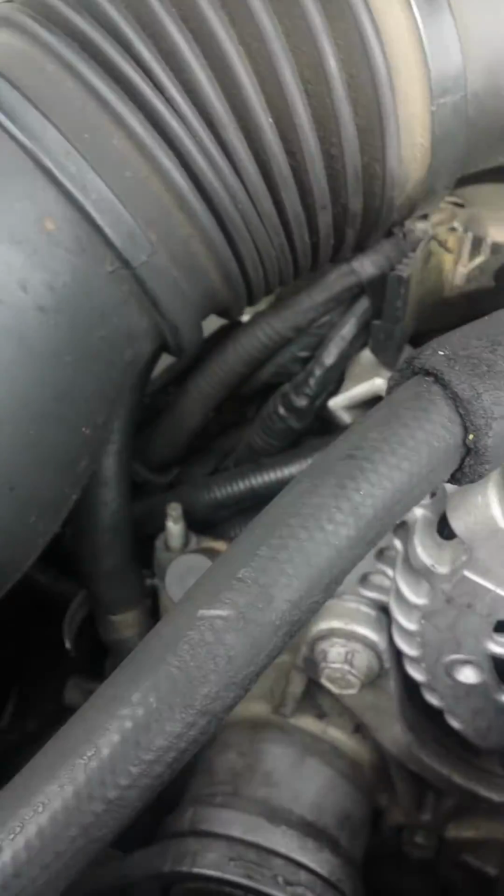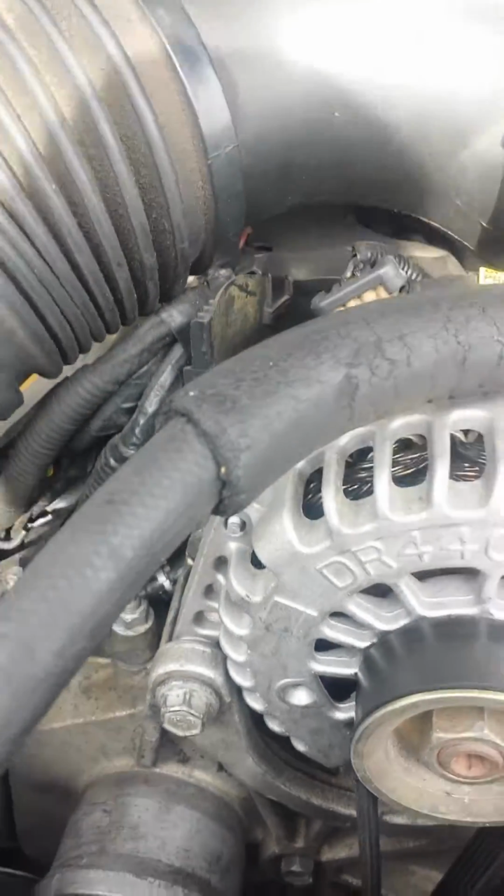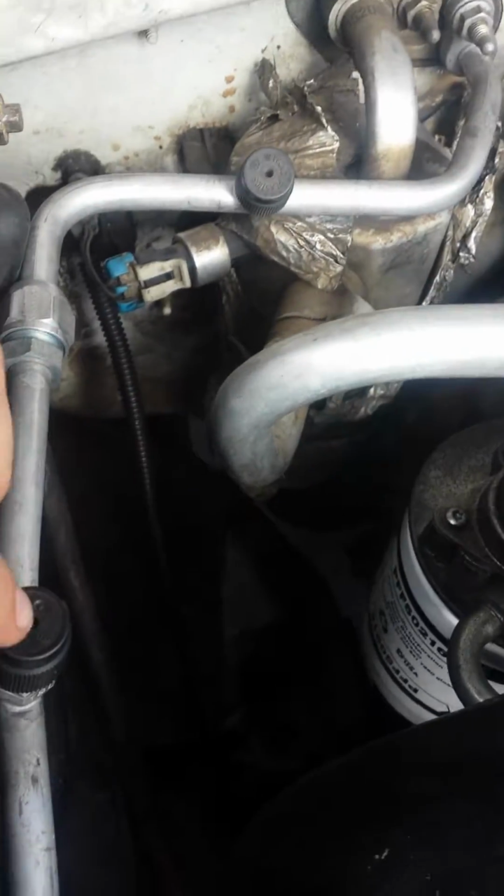So once it goes through the condenser, which is just like a radiator, essentially it's got a bunch of fins, and then the air coming across cools off the Freon. So from the condenser, we have another line on the bottom that is the other high side line. Comes through, down and around, up into here. There's one of your ports, your high side port.